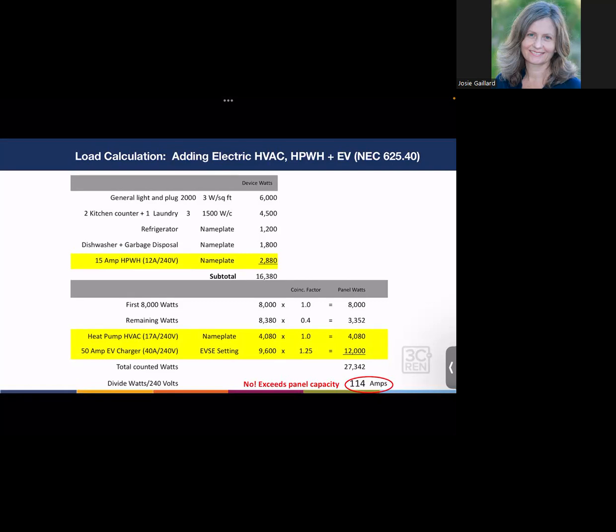Now we apply those coincidence factors, which you can see listed in the second column from the right. These are code described coincidence factors by appliance type. So it says first 8,000 watts, apply that 1.0 coincidence factor for 8,000 panel watts. Then we have the remaining 8,380 watts, applying a coincidence factor of 0.4, and we get 3,352 watts. Now we add in 2 devices that the code tells us have special coincidence factors. So you can see that water heater up above was able to be considered a general load and have that 0.4 coincidence factor applied to it.